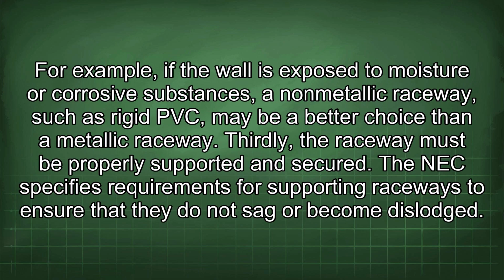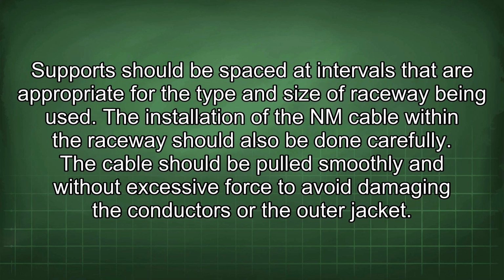For example, if the wall is exposed to moisture or corrosive substances, a non-metallic raceway, such as rigid PVC, may be a better choice than a metallic raceway. Thirdly, the raceway must be properly supported and secured. The NEC specifies requirements for supporting raceways to ensure that they do not sag or become dislodged. Support should be spaced at intervals that are appropriate for the type and size of raceway being used.